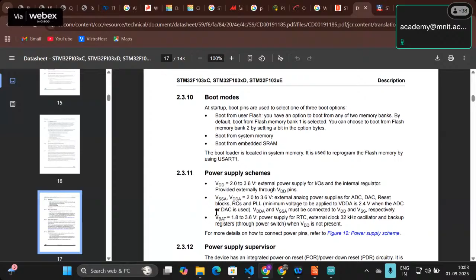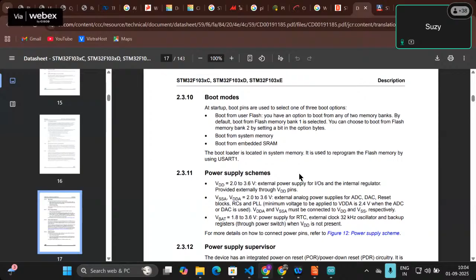It says it requires 1.8 to 3.6 volts for the external clock to work at 32 kilohertz and for the oscillator to back up the registers. So this basically runs from 3.3 volts to 3.6 volts. Now that our PLC has a 24 volt power supply, we can use a 3.3 to 3.6 volt voltage regulator. If the voltage regulator is supplied by a constant 24 volts, only then will it step down the voltage correctly and give it to the microcontroller.